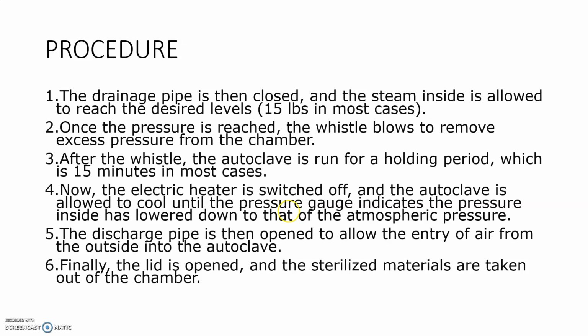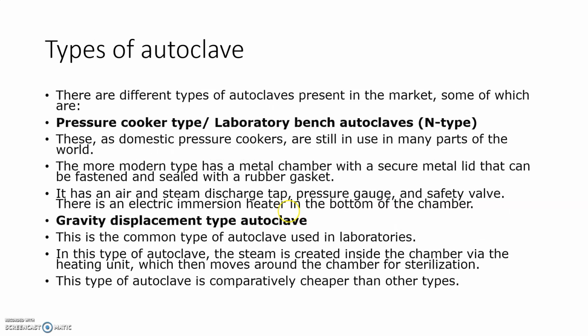The discharge pipe is then opened. We allow the entry of air from the outside into the autoclave. Finally, the lid is opened and the sterilized materials are taken out. So that's about the procedure. Next is different types of autoclave.